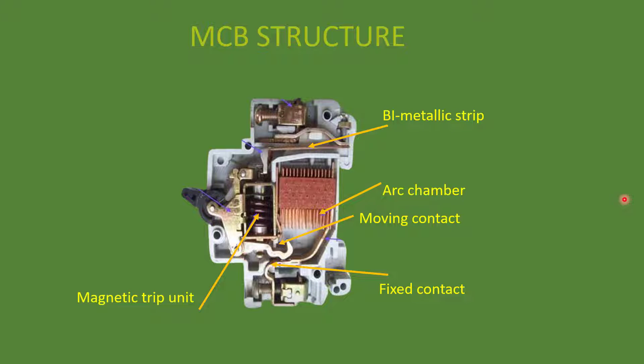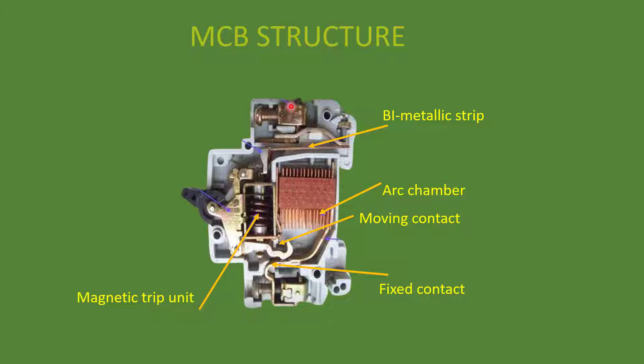Another type of protection the MCB offers is overload protection. A bimetallic strip is used for this — it is made of two metal combinations with specific properties. If the load increases, the current through the bimetallic strip also increases, causing more heat to be produced. Due to this heat, the bimetallic strip bends, which disconnects the contact and interrupts the power supply. This is how the overcurrent protection mechanism works in an MCB.